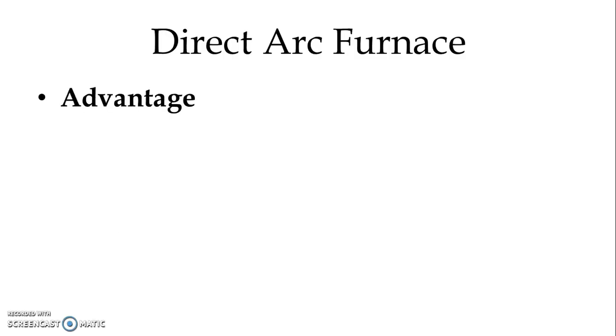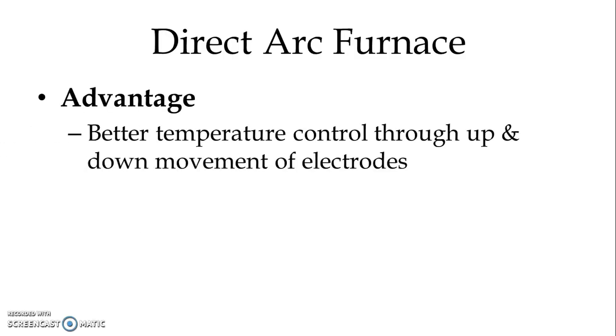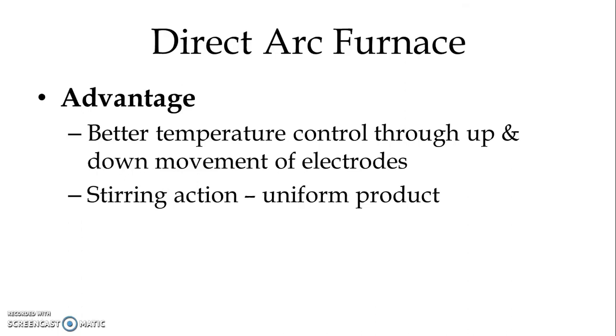Arc is produced in the charge itself and that is why more heat and high temperature is produced in the direct type of Arc Furnace. Advantages of Direct Arc Furnace: better temperature control is possible through up and down movement of the electrodes. Electrodes can be moved vertically to adjust the distance between the charge and electrodes. We can short-circuit the electrodes with the charge and then move them slightly upward to maintain the arc between electrodes and charge. Because current passes through the charge itself, stirring action is possible, and that is why we get a uniform product.